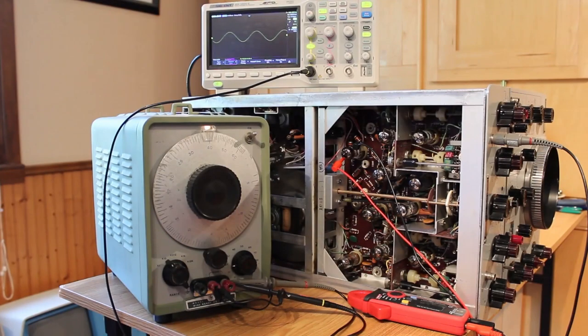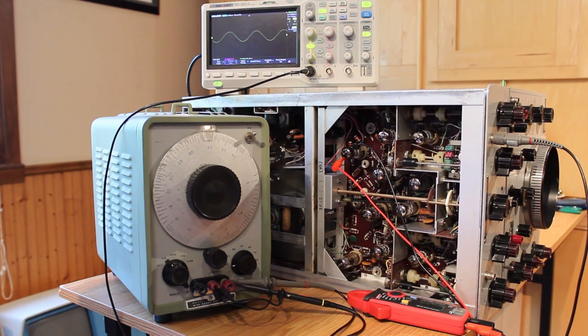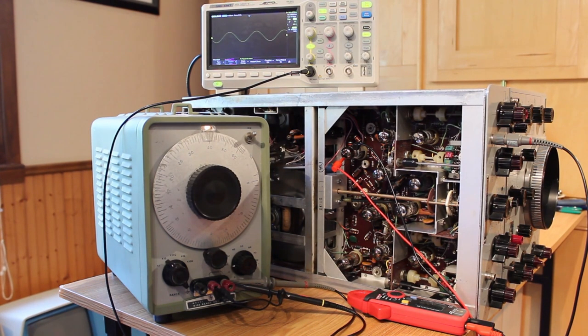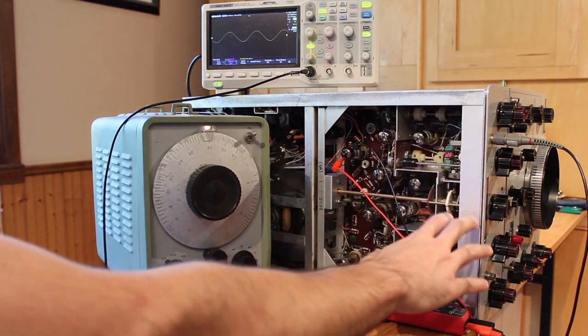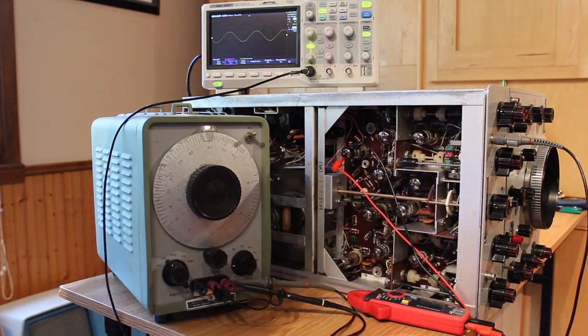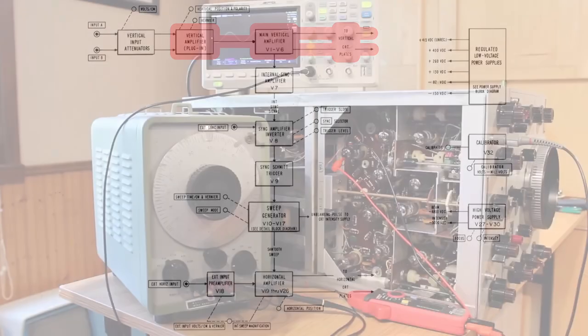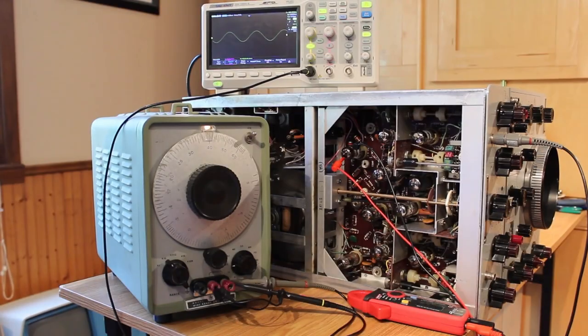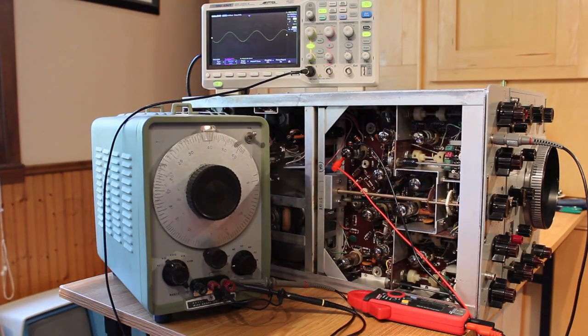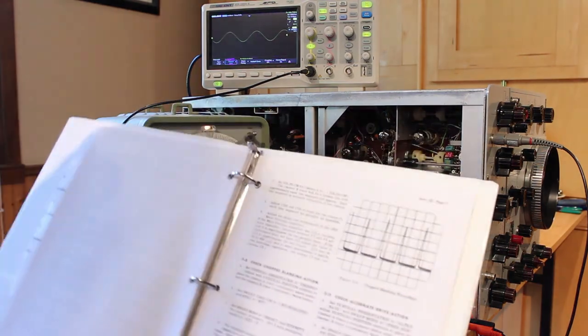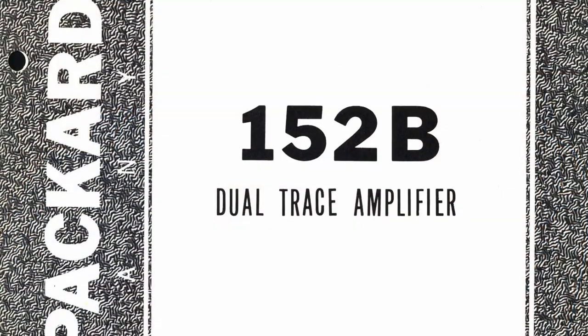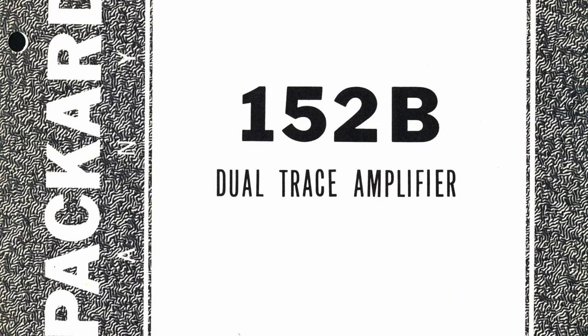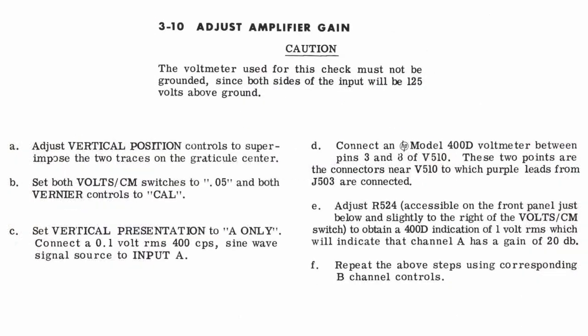All right, I've been spending hours trying to get this thing to where I want it to be. So vertical amplification happens one is on this plug-in module on the bottom, and that's what we're looking at right here. And then the other is there's a main amplifier on the chassis itself that connects directly up to the CRT deflection plates. And so the first step is making sure that the plug-in unit is doing what it's supposed to do. And it just so happens that in the manual for the plug-in unit, this is HP 152B, there is a procedure for adjust amplifier gain.